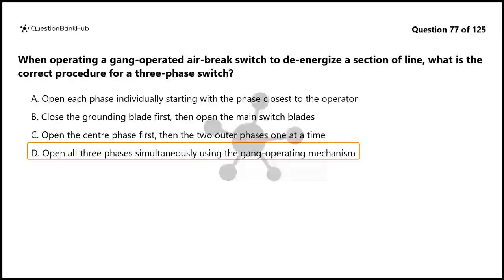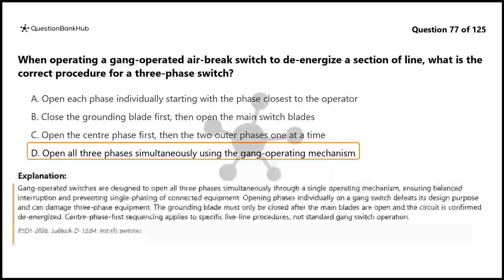The correct answer is D. Gang-operated switches are designed to open all three phases simultaneously through a single operating mechanism, ensuring balanced interruption and preventing single-phasing of connected equipment. Opening phases individually on a gang switch defeats its design purpose and can damage three-phase equipment. The grounding blade must only be closed after the main blades are open and the circuit is confirmed de-energized. Center phase first sequencing applies to specific live-line procedures, not standard gang switch operation.